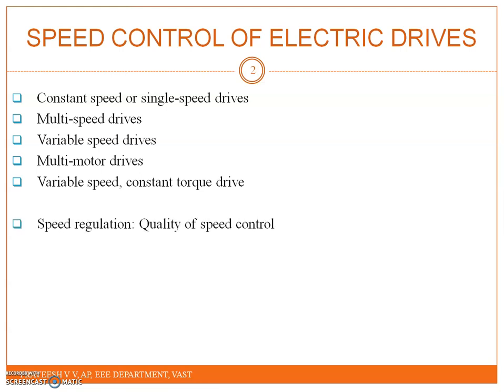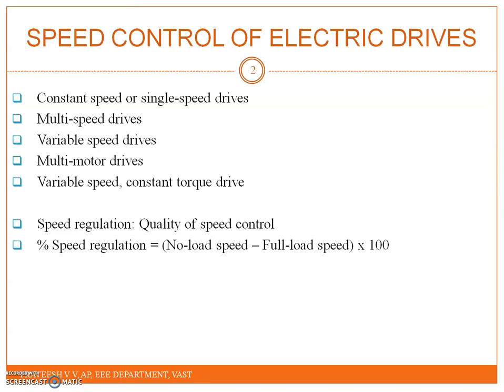Speed regulation is related to the speed of an electric drive. Speed regulation is a standard comparison defined as: no load speed minus full load speed, divided by full load speed, multiplied by 100.